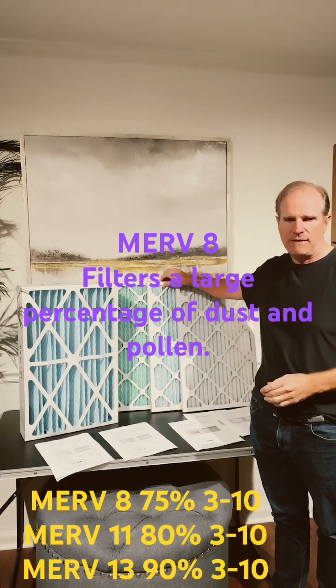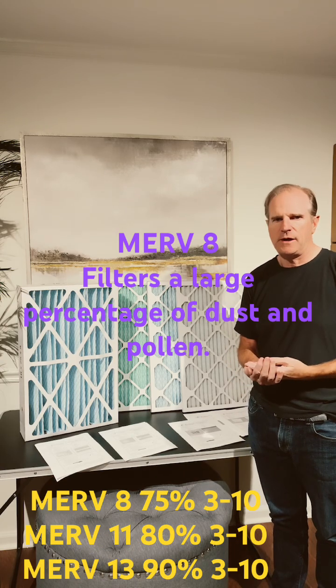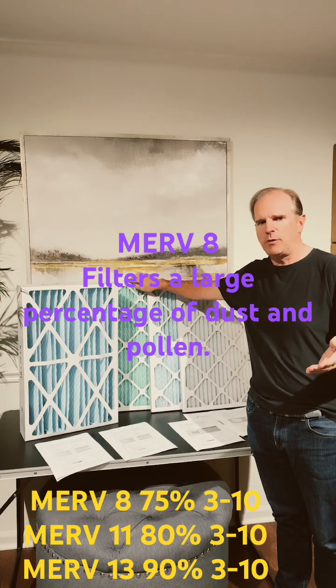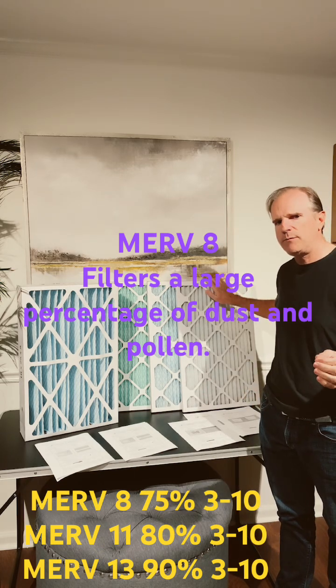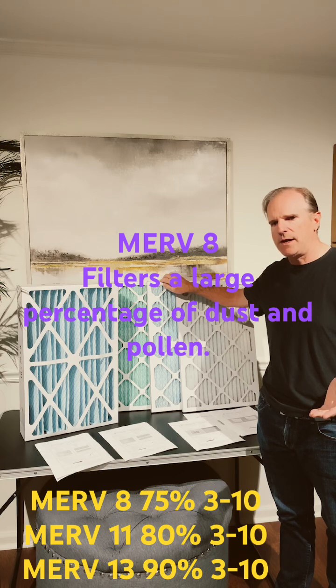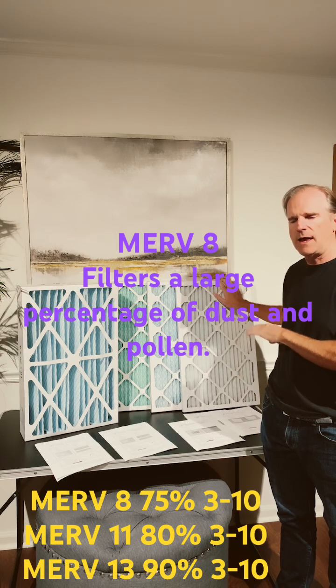As you go up to a MERV 11, the blue filter, it's going to filter out a much larger percentage of those particles — 85% of those particles. And then on the MERV 13, 90% of those particles. But as you go to the very small particles, 1 to 3 microns, the MERV 8 is only going to filter out 20%, where the MERV 11 will filter out 65%. That's over three times what the MERV 8 will filter out.